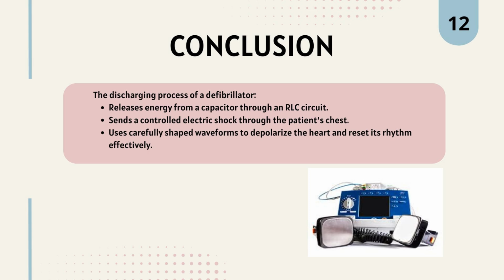In conclusion, the discharging process of a defibrillator releases energy from a capacitor through an RLC circuit, sends a controlled electric shock through the patient's chest, and uses carefully shaped waveforms to depolarize the heart and reset its rhythm effectively.